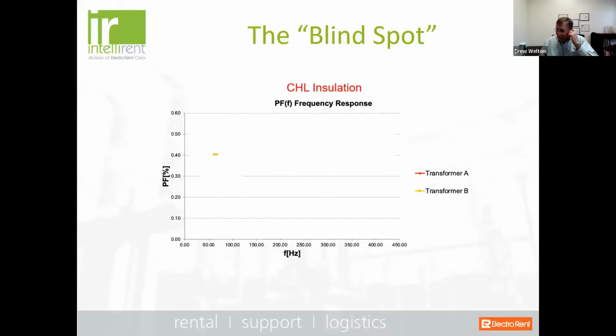Okay, so here's a case study we did with two similar transformers, transformer A and B, and we did a CHL measurement here, and you can see that they're both, at about 0.4, slightly elevated, but maybe not a cause for concern. So if we extend the frequency range, you can see that transformer A has a higher indication of conductive losses than transformer B. So what does that mean? Well, if we do what's called a dielectric frequency response measurement, we'll get into this a little bit later on, we determined that in transformer B, we only had a 1% moisture content. And that is certainly acceptable.